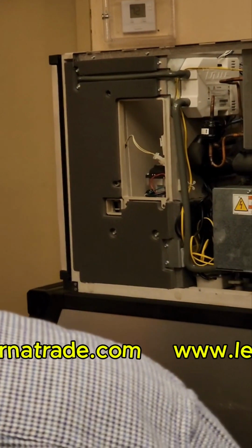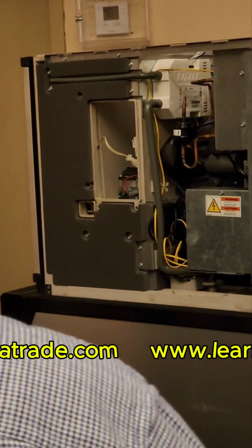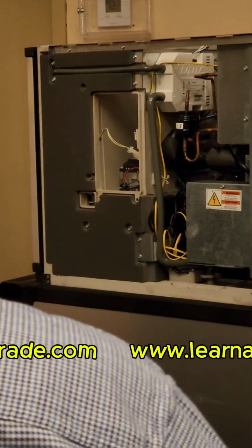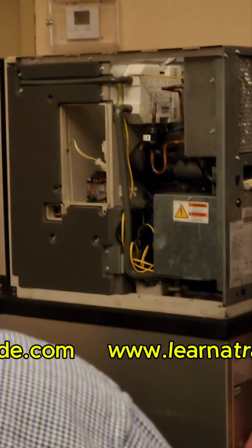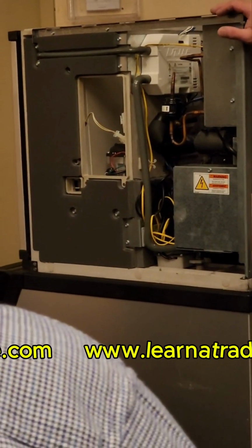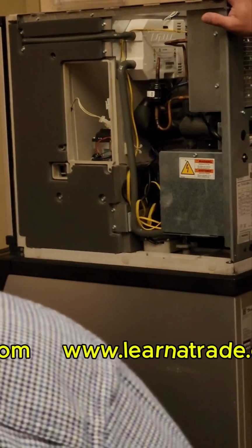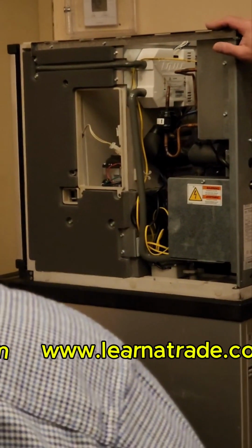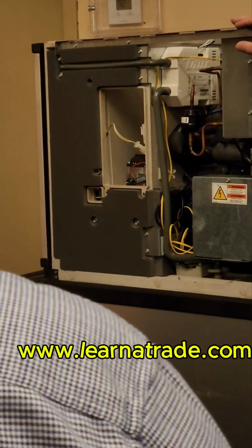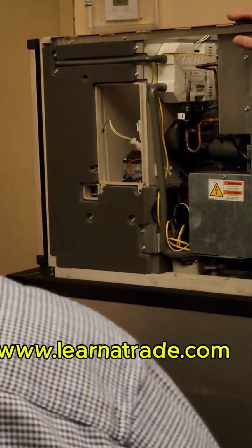What about the evaporator grids themselves? Sometimes the horizontal and vertical pieces get loose on other brands. Yeah, I expect that to happen eventually. Between people using chlorine, too much chlorine, or a non-nickel-safe cleaner, it eats up the nickel, and then it gets down to the brazing material.